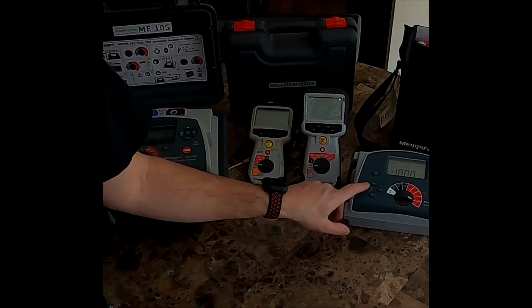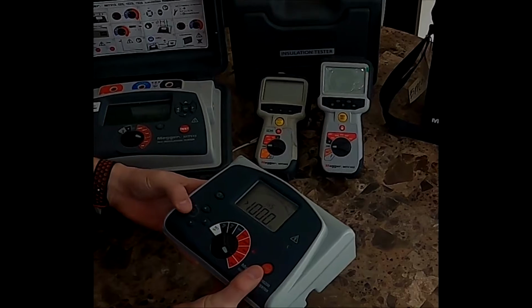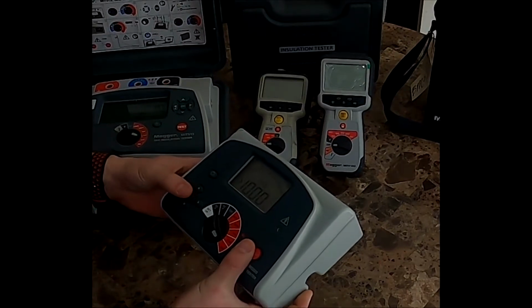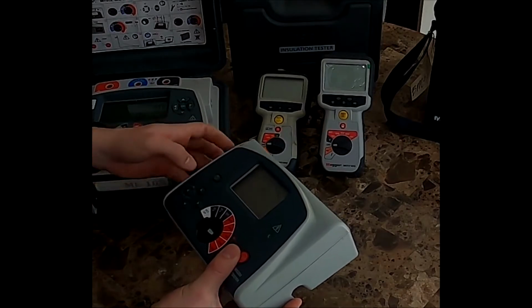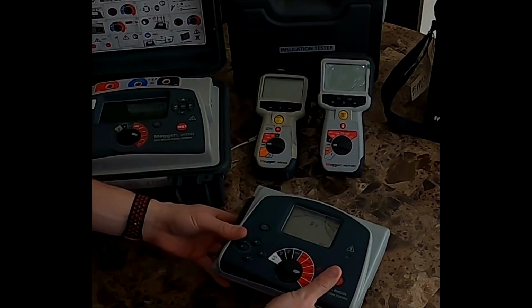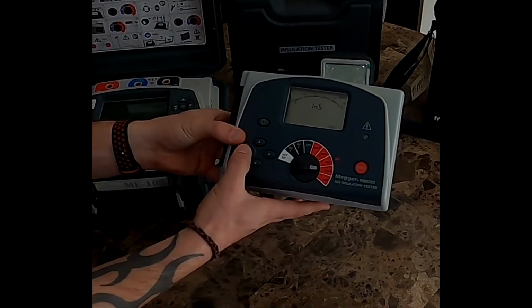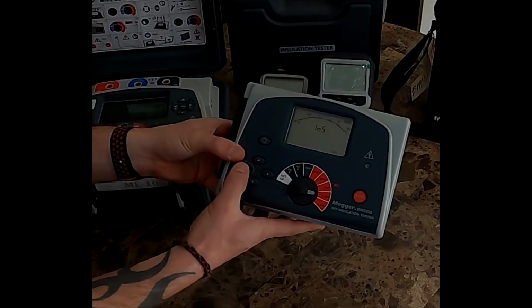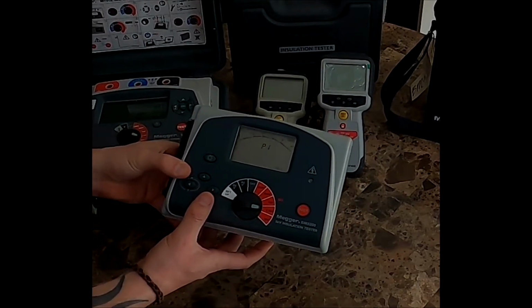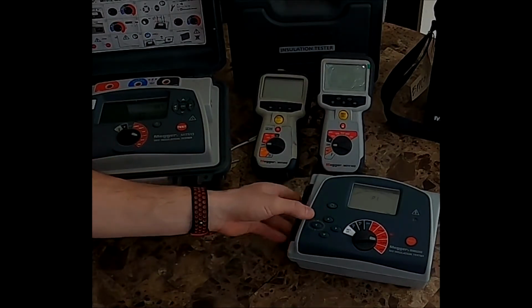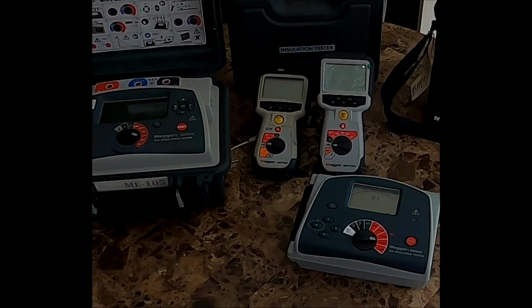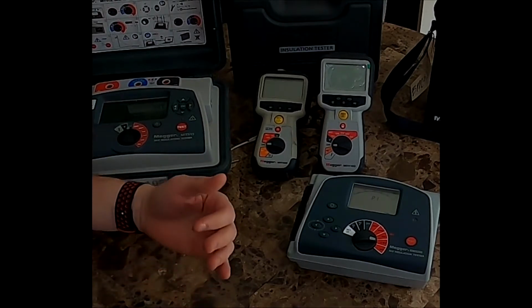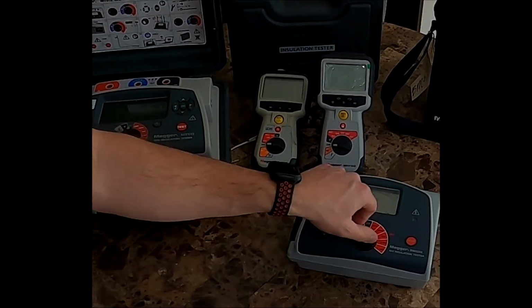This one you have a PI option, which you can see PI time or just insulation. In the PI, I believe it'll give you the dielectric absorption ratio, which is your 1 minute reading divided by your 30-second reading. A PI would be your 10-minute reading divided by your 1 minute reading. So those two values are pretty important when it comes to transformers or even motors. Cables, if you're doing a 10-minute cable test.